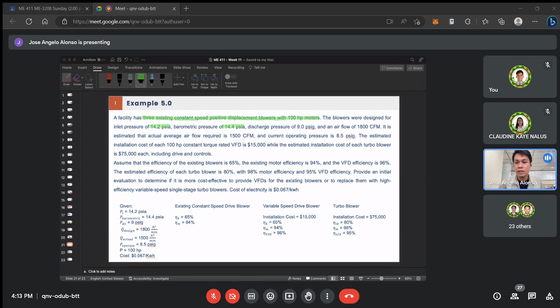So it is estimated daw na yung actual average airflow is 1,500 cubic feet per minute lang. And the current operating pressure is 8.5 psig. So sinasabi dito, class, na yung actual average airflow na nire-require ng system kung saan man naka-install yung ating blower is just 1,500 CFM. However, since constant speed ito, meaning fixed drive, whatever happens, continuously and constantly magpo-provide siya ng 1,800 CFM. Kasi nga, hindi naman natin mababago yung speed ng motor, constant speed siya. So, 100% continuously magpo-provide ito ng 1,800 CFM.